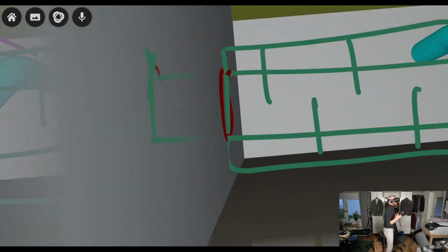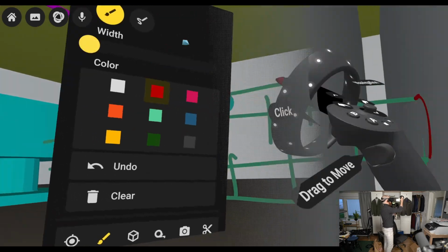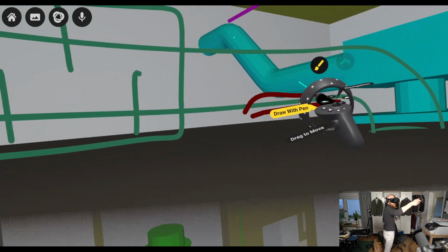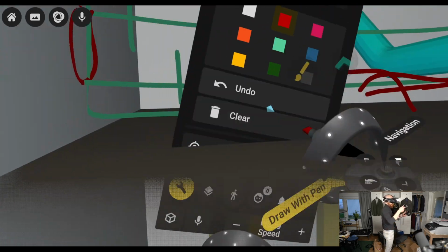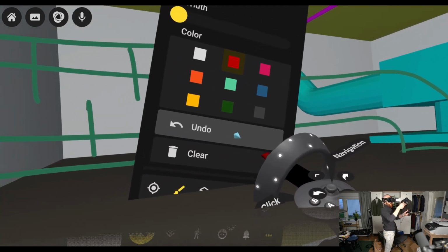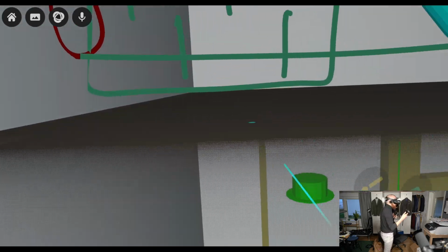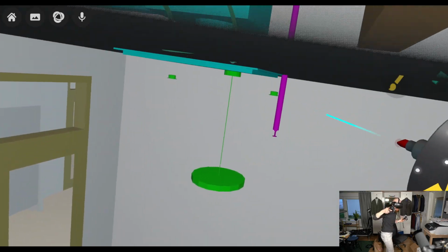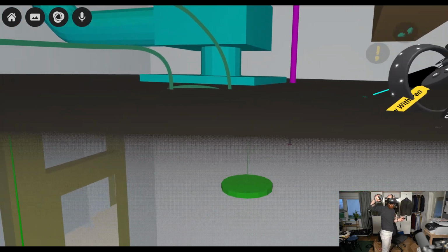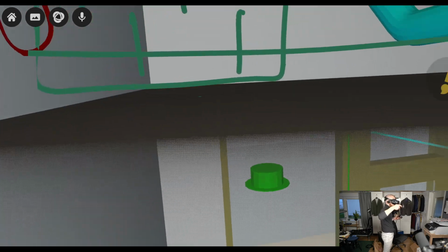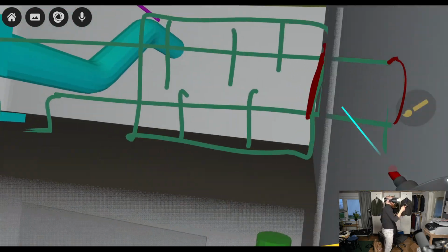But in this case, if you have break-in and break-out transmission now, it's going to take place here. And boom, it's going to hit the silencer. And great, you got it. This is a very good way. And if you want to make this even better, in this case we have some kind of suspended ceiling, it looks like here, a thin one. But let's say that this one would be a gypsum ceiling as well. Then that would also completely kill the break-in, break-out transmission paths.